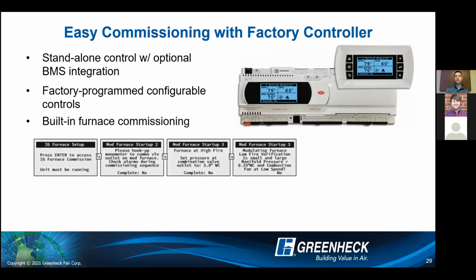Another nice thing is we have the built-in furnace commissioning. So as you have startup techs or contractors going out on that roof, commissioning this equipment, we have a really nice furnace commissioning menu that is a step-by-step guide to make sure that they're doing the right things to commission that furnace and to make it easier at that time. So it's going to say, you know, is this gas LP or natural gas? Do you have your manometer? Do you have it hooked up to this valve and this valve? And it's going to walk you through step by step.